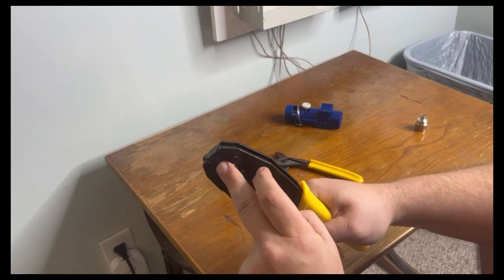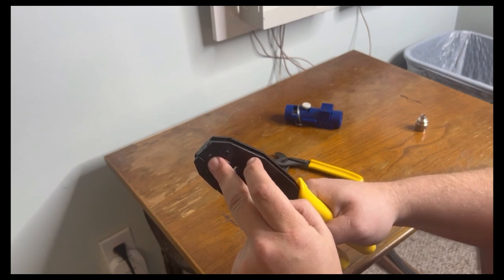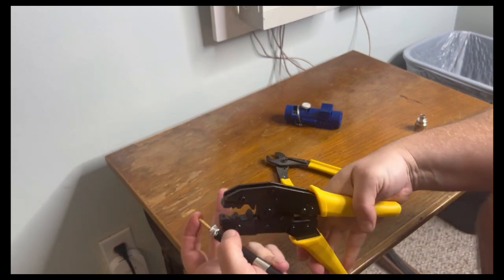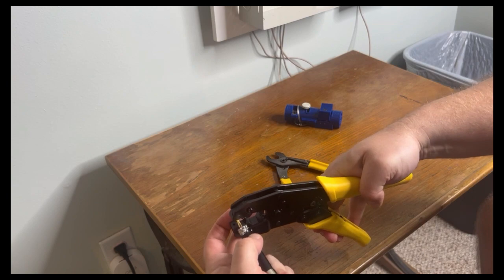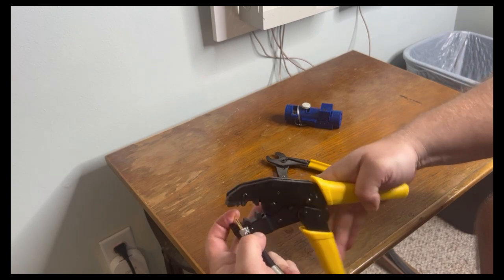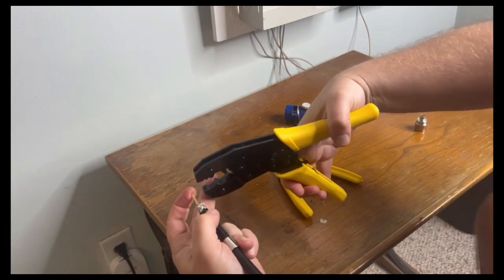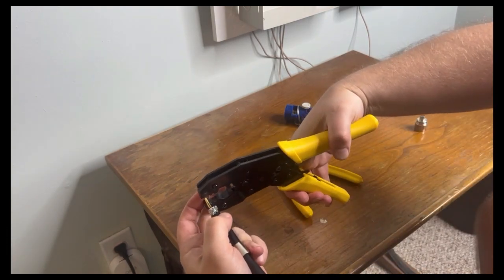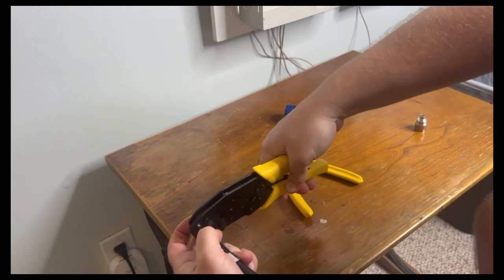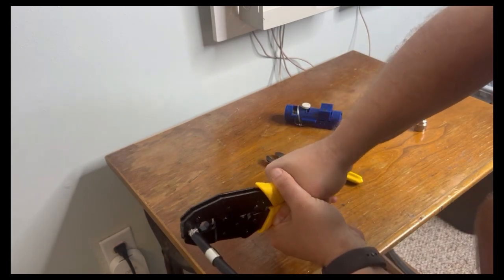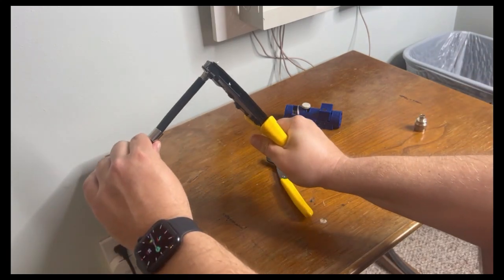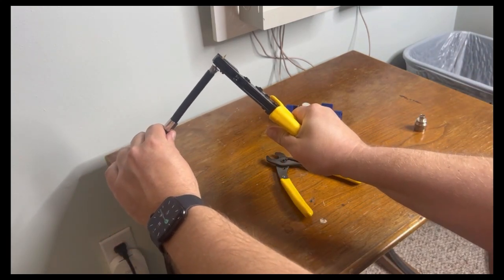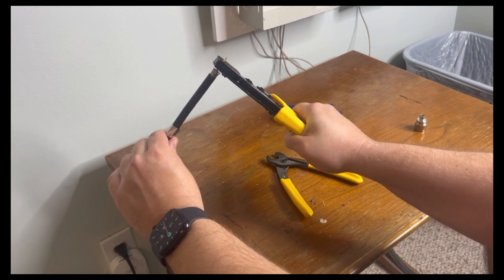We're going to use the front-most hole to crimp the center pin onto this cable. Crimp the center pin until it releases. Make sure the tool is perfectly perpendicular so you don't break the pin off.